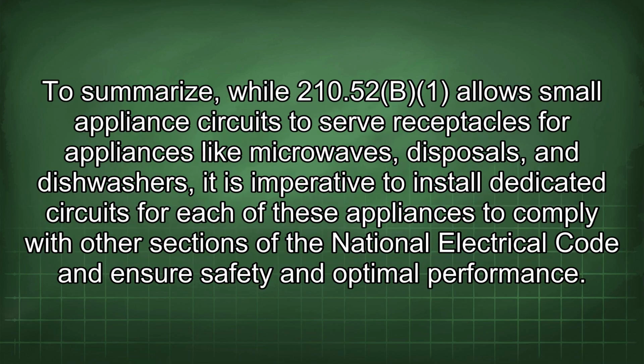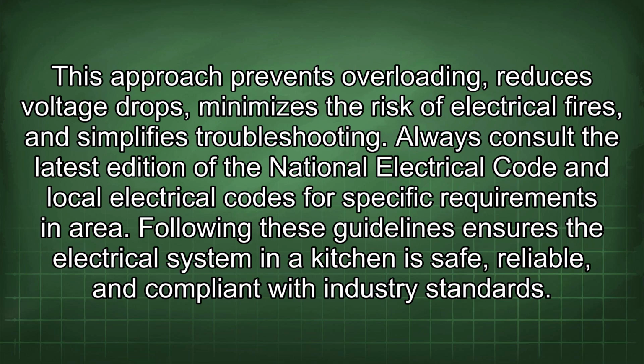To summarize, while 210.52 allows small appliance circuits to serve receptacles for appliances like microwaves, disposals, and dishwashers, it is imperative to install dedicated circuits for each of these appliances to comply with other sections of the National Electrical Code and ensure safety and optimal performance. This approach prevents overloading, reduces voltage drops, minimizes the risk of electrical fires, and simplifies troubleshooting. Always consult the latest edition of the National Electrical Code and local electrical codes for specific requirements in your area. Following these guidelines ensures the electrical system in a kitchen is safe, reliable, and compliant with industry standards.